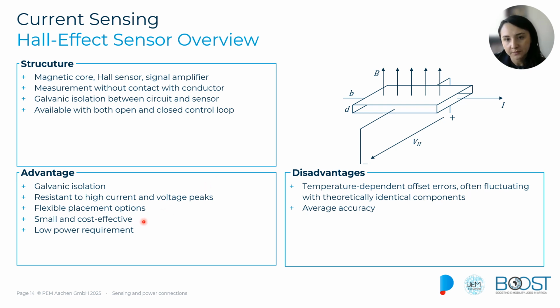On the other side, some of the disadvantages, and one of the most important, is the offset. The circuit and the sensor itself has electrical and magnetic offsets that are highly dependent on temperature, and that at the end means that the measurement accuracy is affected. That is one of the biggest problems it has.